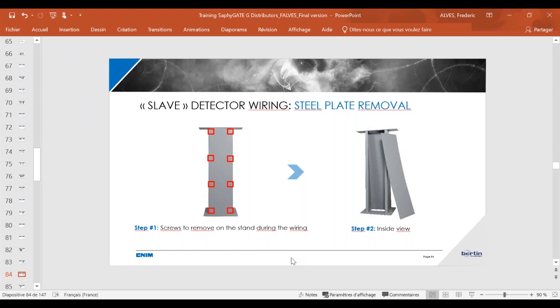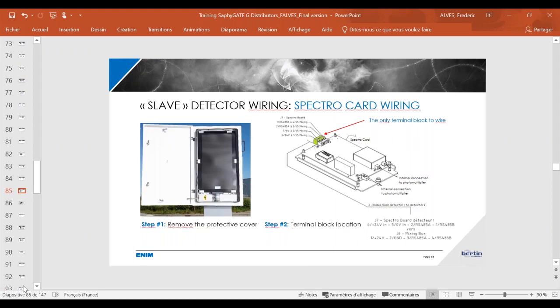The same as for the master detector, you have first on the slave detector to remove the screws on the back side of the stand. So another time you have to remove 8 screws in order to remove this plate. And concerning the slave detector, it is very simple, because you only have one cable to wire. This is the cable which comes from the master detector. It has to be connected on the Spectro card as presented below. The only terminal block you have to connect is the green one.